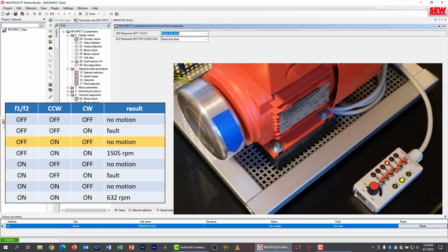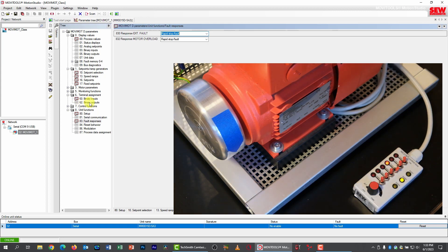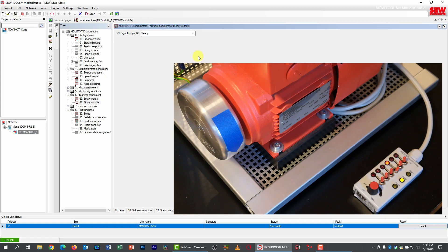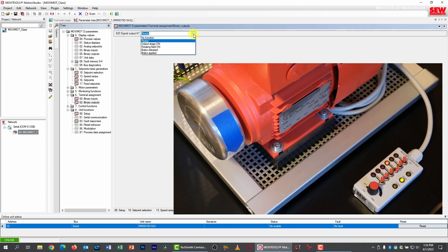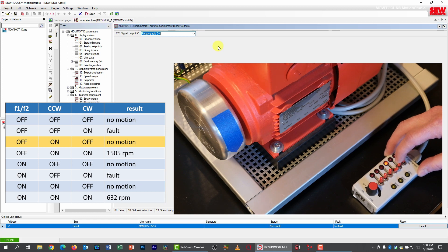If you enable the external fault sensor, it's probably a good idea to associate the fault with the rapid stop ramp. I turn the fault switch back on, disable the drive, and reset the fault. Then I go to parameter group 8, subgroup 3, fault responses — the external fault's response is currently normal stop. I change this to rapid stop with a fault message, fire up the drive again, trigger a fault, and this time it stops in about half a second — which is what we programmed in parameter 136.